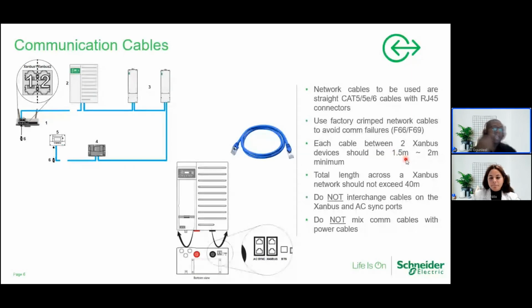Then across the entire Xanbus network. So let's assume you have one inverter, two charge controllers, the AGS, and the inside local device. Across the entire Xanbus network, even if you're going to have more inverters, more charge controllers, or more other accessories, the entire distance should not exceed 40 meters, because there's also a tolerance. There's a minimal tolerance, which is 1.5, and there's a maximum tolerance, which is 40 meters.